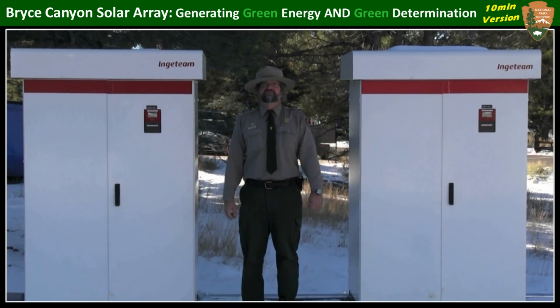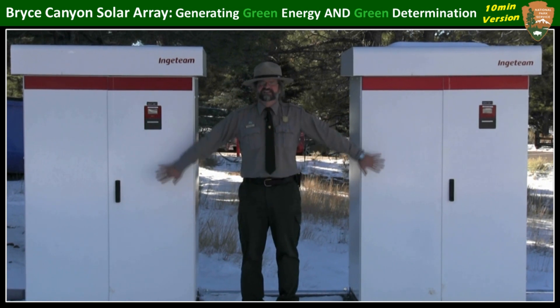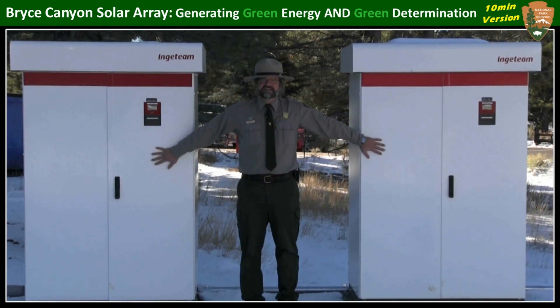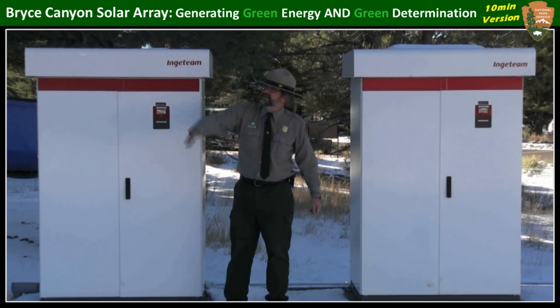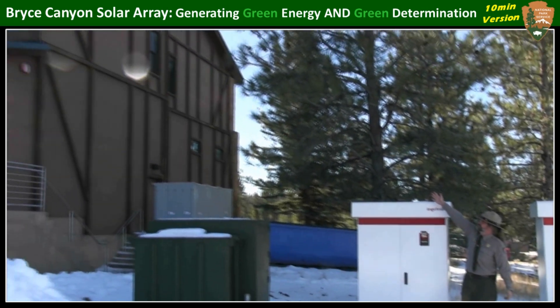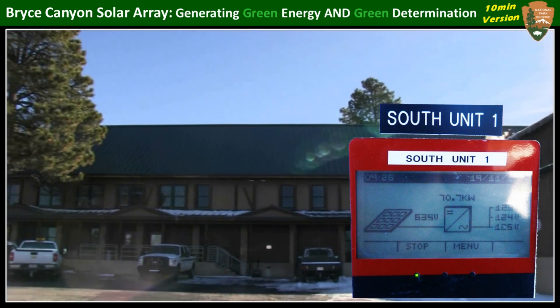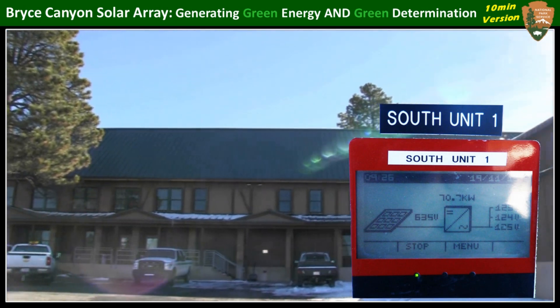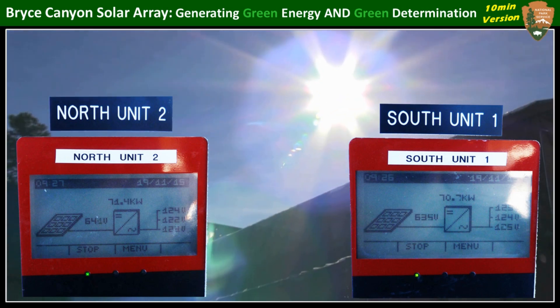Each tracker delivers an average rate of 75 kilowatt hours of electricity to its own inverter. These inverters, made by Ingeteam, convert that energy to alternating current with less than one percent energy loss, leaving more than enough electricity to power the entire 32,000 square foot Bryce Canyon Visitor Center and Administration building. As we check the inverters now, the south tracker is producing 70.7 kilowatts, where the north one is at 71.4 — and that's a lot of energy for this early in the morning.